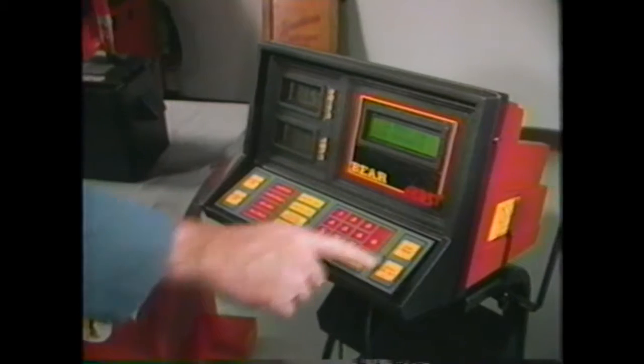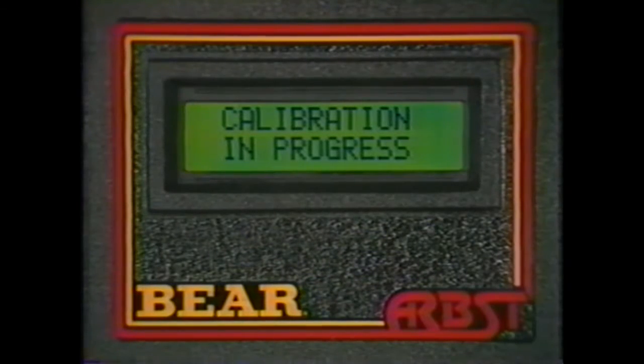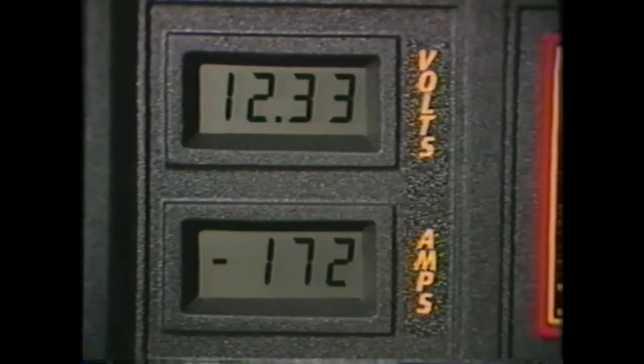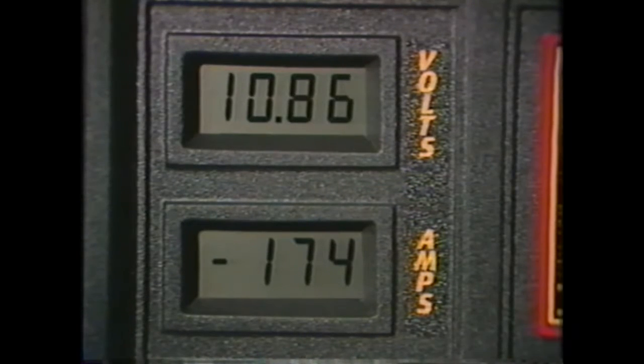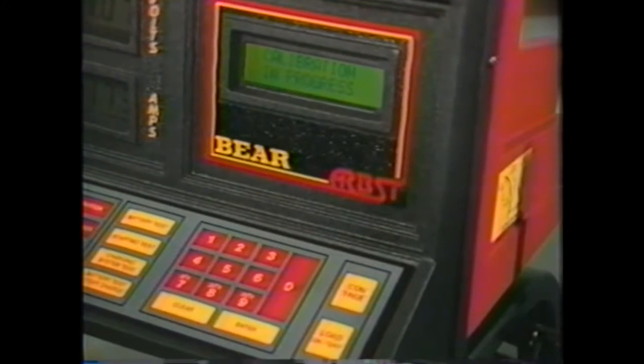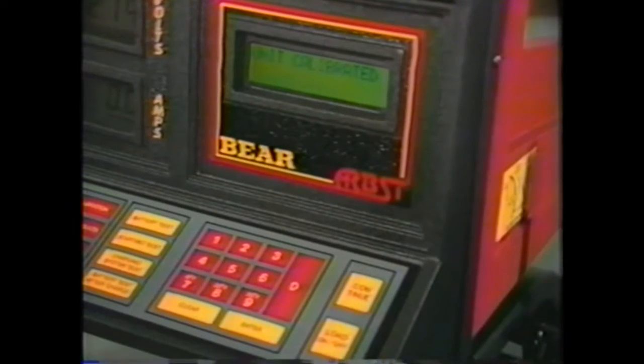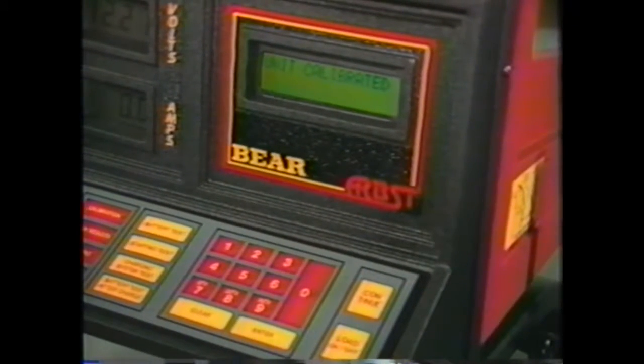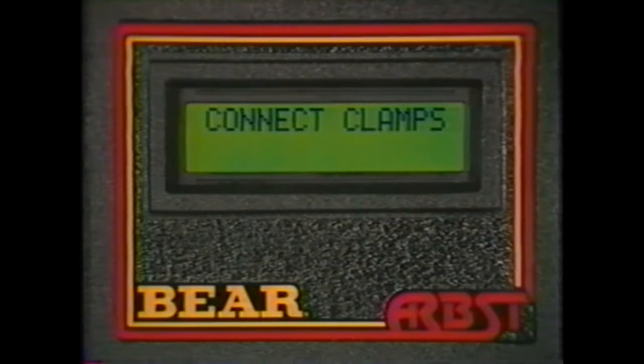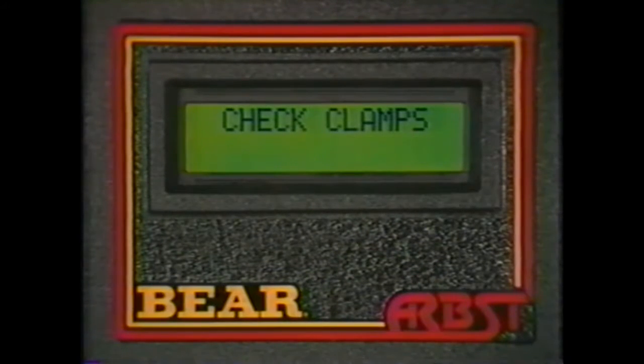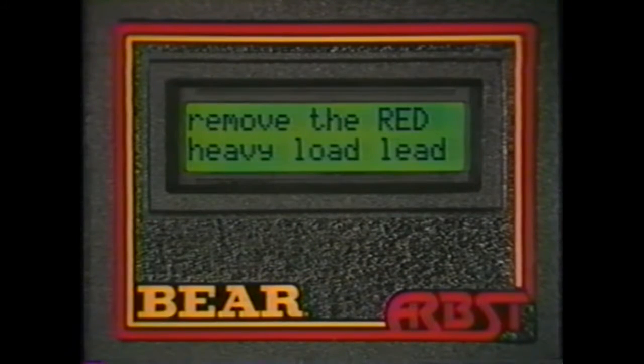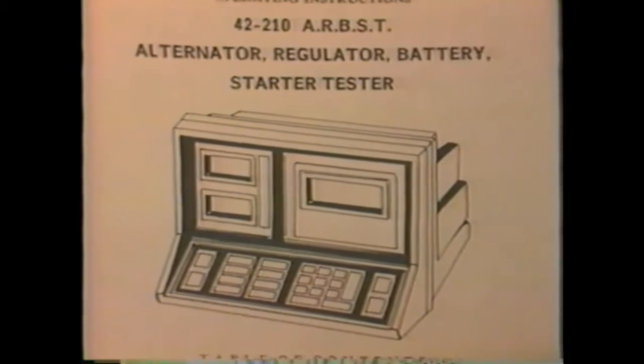When all the leads are properly connected according to the diagram, press Continue. The display will say Calibration in Progress. The tester places a load on the battery during calibration, which is used to calibrate the amps probe. The whole procedure only takes a few moments. When calibration is complete, the display says Unit Calibrated. The calibration procedure is now complete. If any message is displayed that we have not covered during the calibration procedure, simply do what the message says. If you need more information, refer to your ARBST Operator's Manual for details.